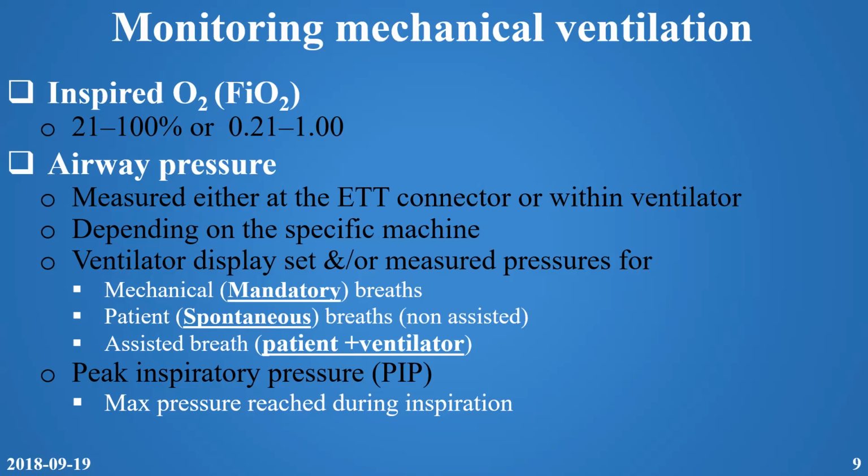So based on the airway, which is the pressure provided to the baby above atmospheric pressure. Any pressure pushed by the machine to the baby above atmospheric pressure is called airway pressure. And for the machine, the atmospheric pressure at sea level is 760 millimeters of mercury, or 1034 centimeters of water, or 101 kilopascals, all the same number but different measuring units. Anything above this provided by the machine to the baby is called airway pressure.